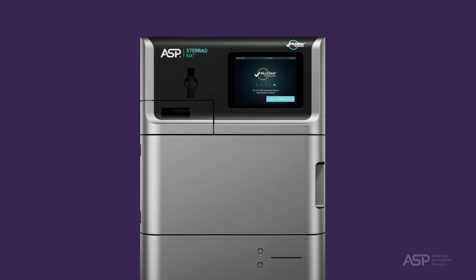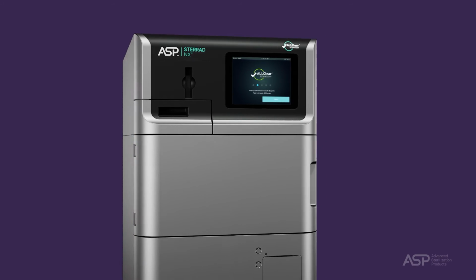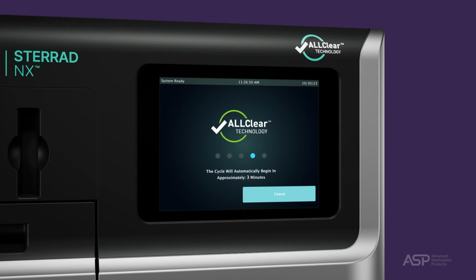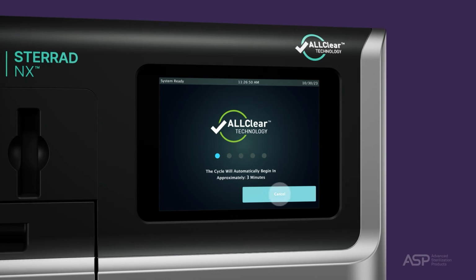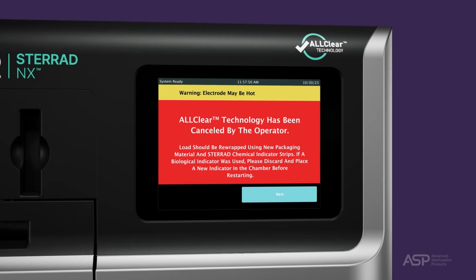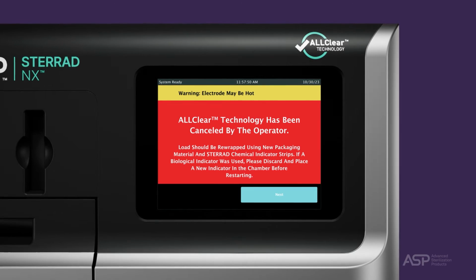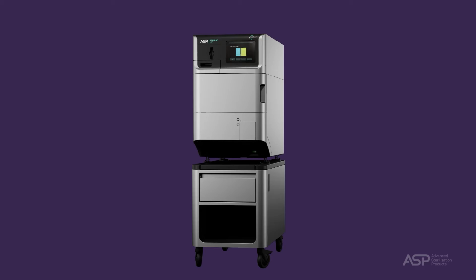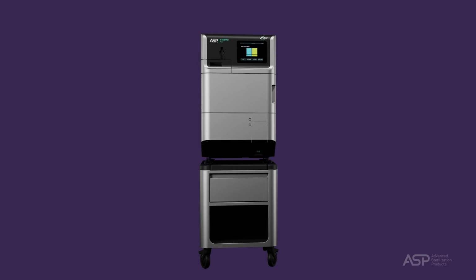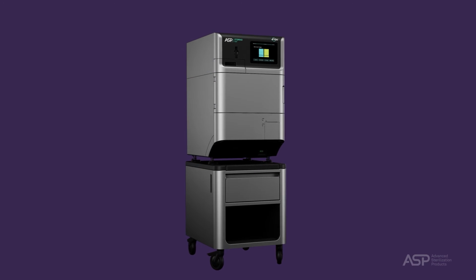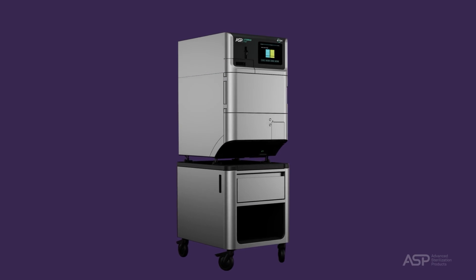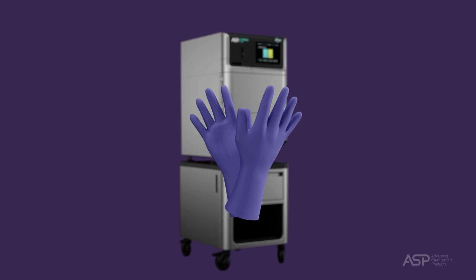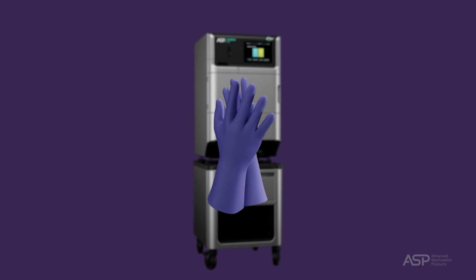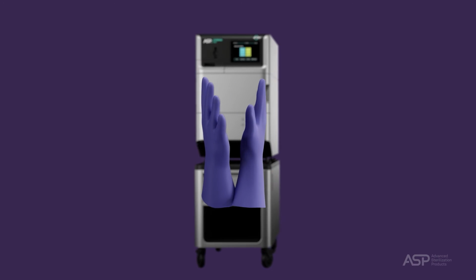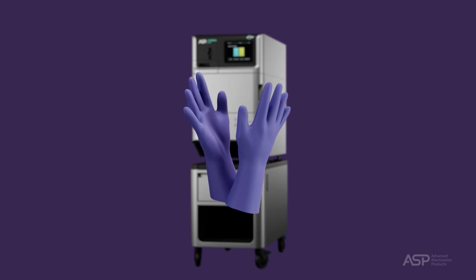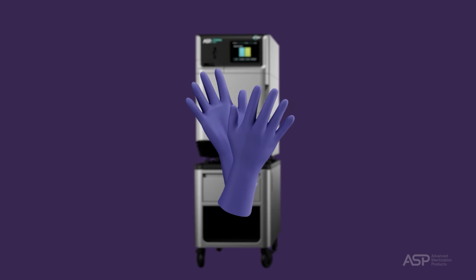There may be occasions when it is necessary to cancel a cycle before it is completed. To cancel a cycle, simply touch the Cancel Cycle button. The screen will display a confirmation message because hydrogen peroxide may be present. As a precaution, when handling any part of the system or load items that have been exposed to hydrogen peroxide, please wear the appropriate PPE, chemical-resistant latex, PVC/vinyl, or nitrile gloves. Refer to the glove manufacturer's instructions for use for more information.